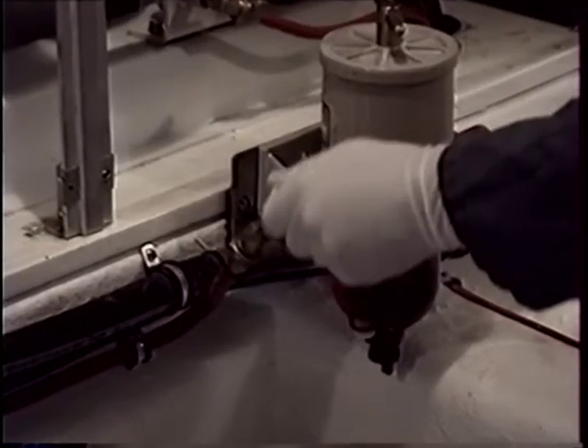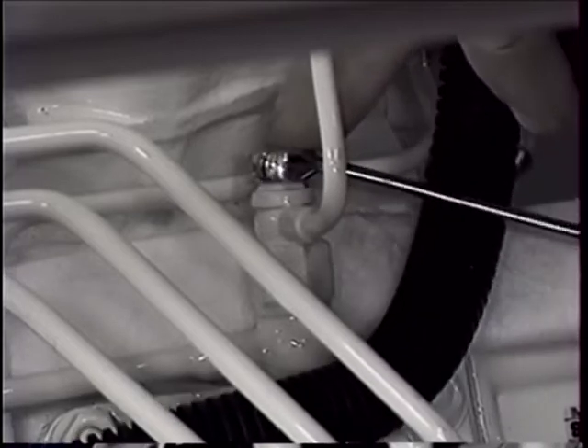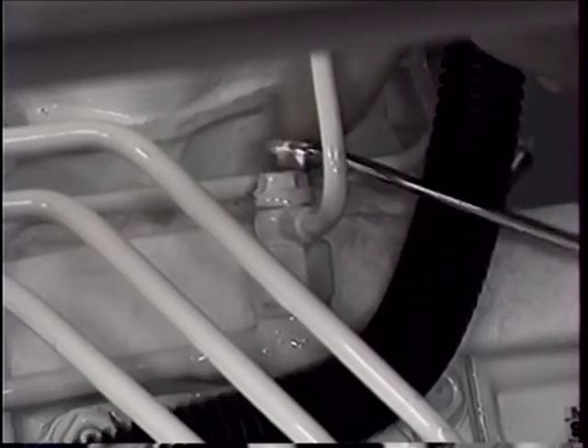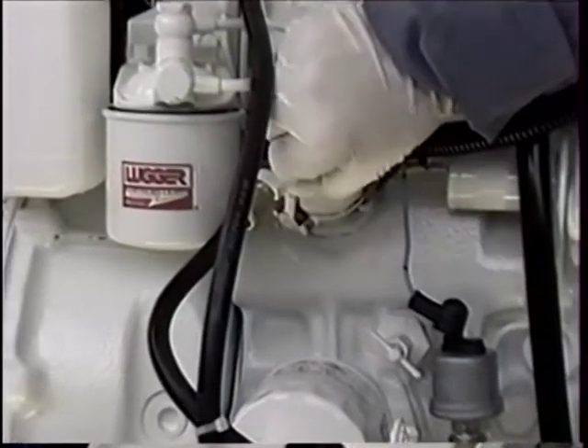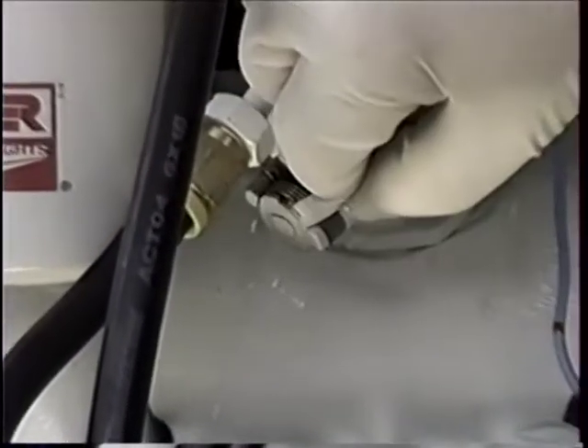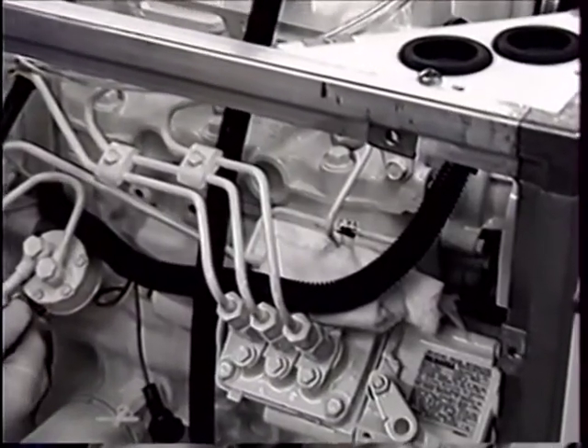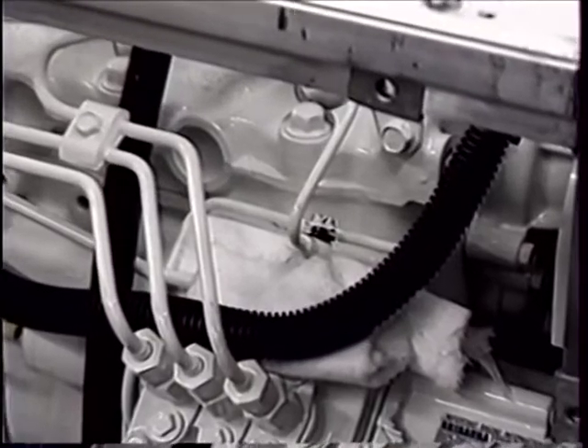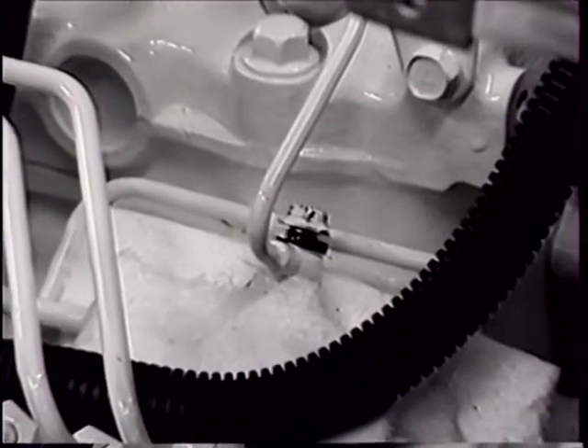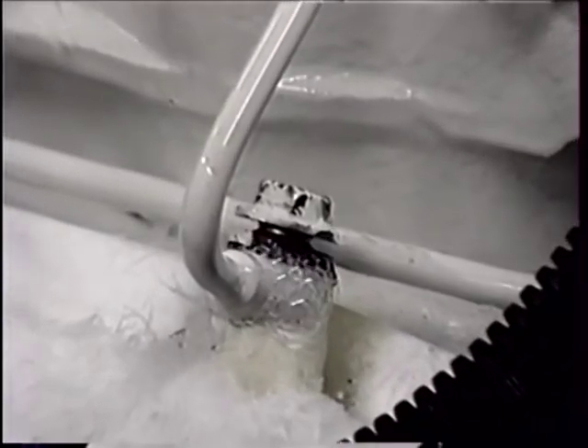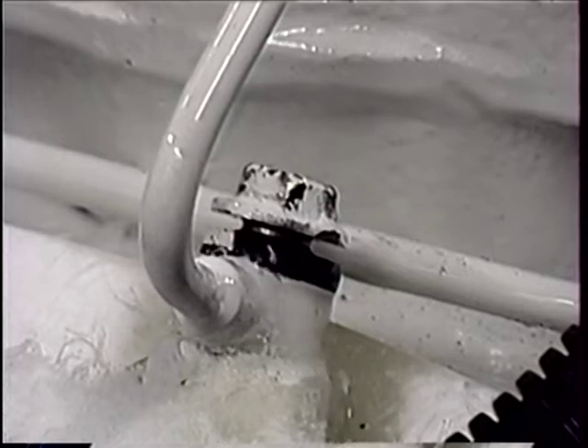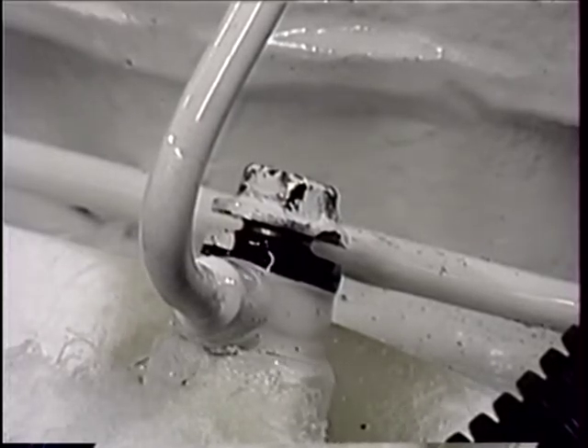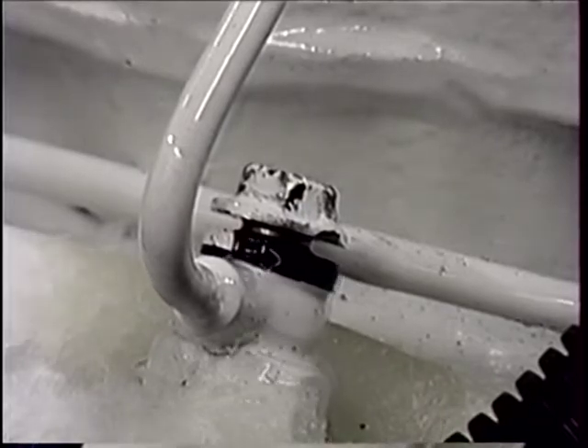Turn the fuel shutoff valve back on. Place a small piece of absorbent pad around the bleed screw to soak up spillage. Loosen the bleed screw. The system is bled using the priming lever of the fuel lift pump. Pump the priming lever until all signs of air are removed. Initially, you will get fuel out of the bleed screw because there is a small amount of fuel in the line between the filter and the bleed screw. Continue pumping until all air escapes and fuel once again comes out. Retighten the bleed screw.